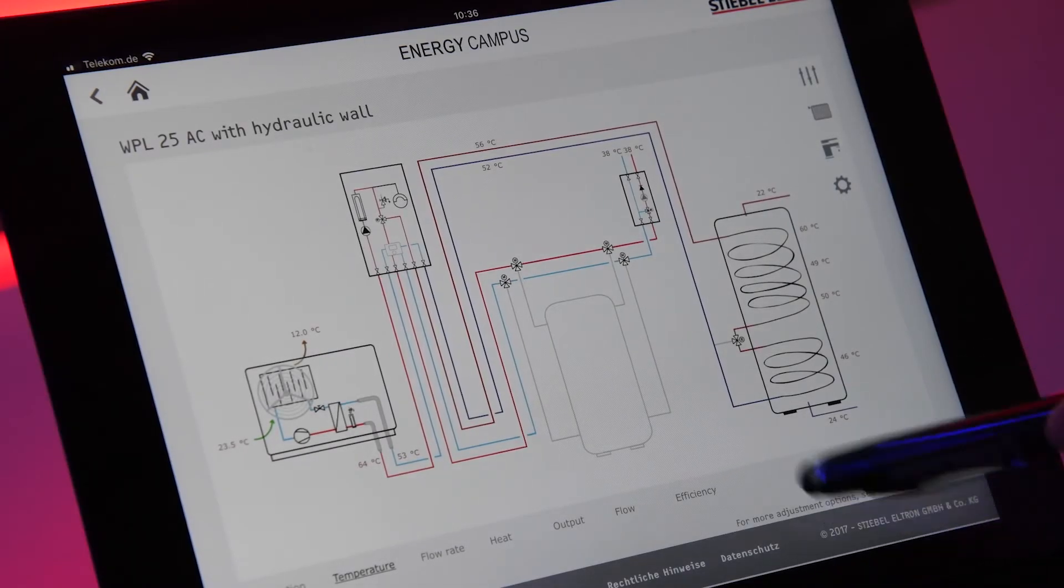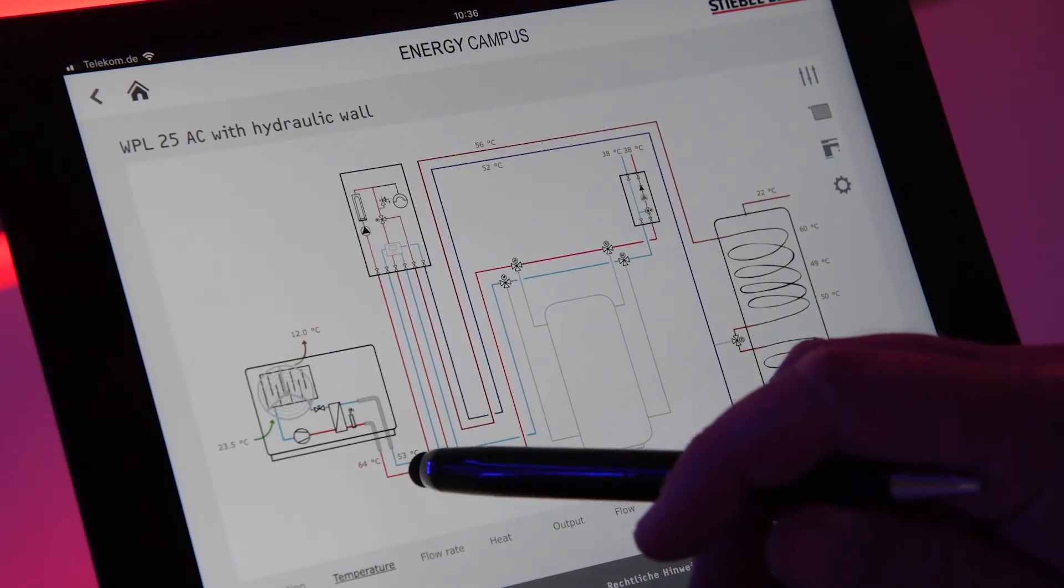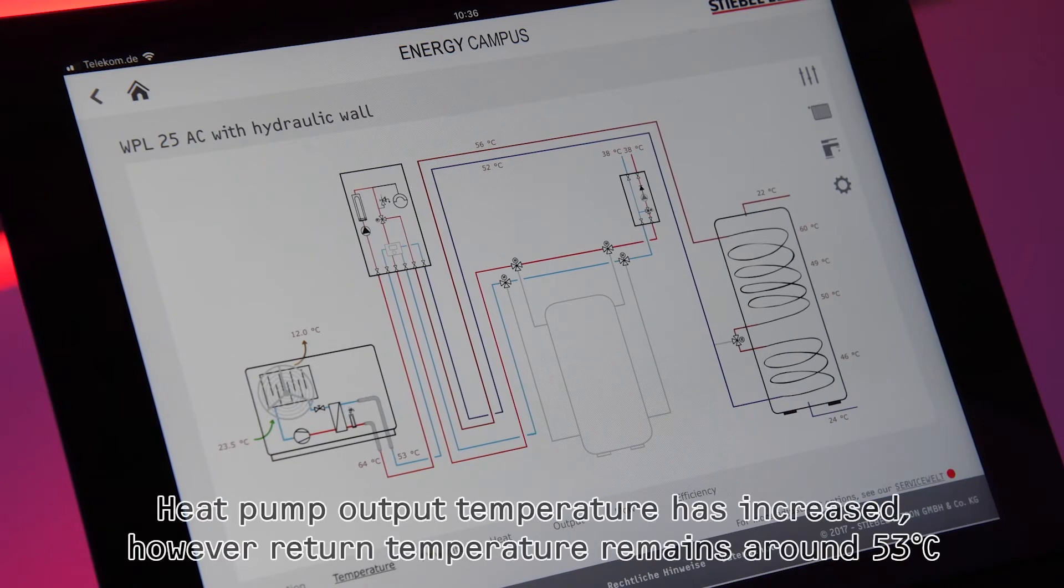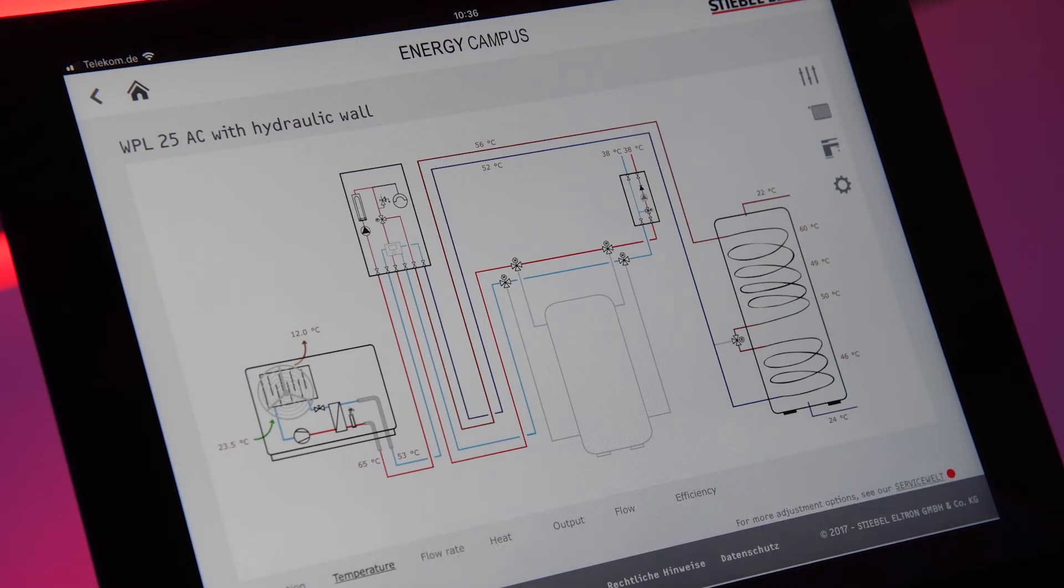Okay, have a look what has happened now. Our return temperature from the cylinder is still 53 degrees C but the flow temperature out of the heat pump has increased now to 65 degrees C. So before we had a delta T of 6 Kelvin, now we have a delta T of 12 Kelvin.